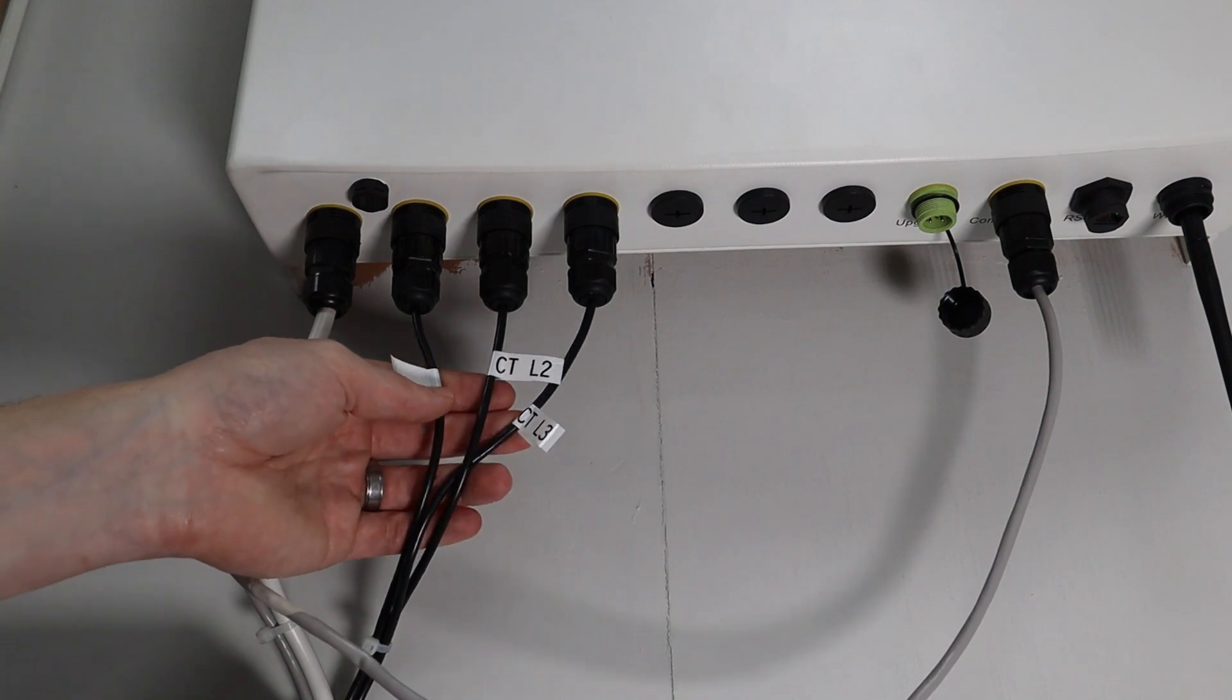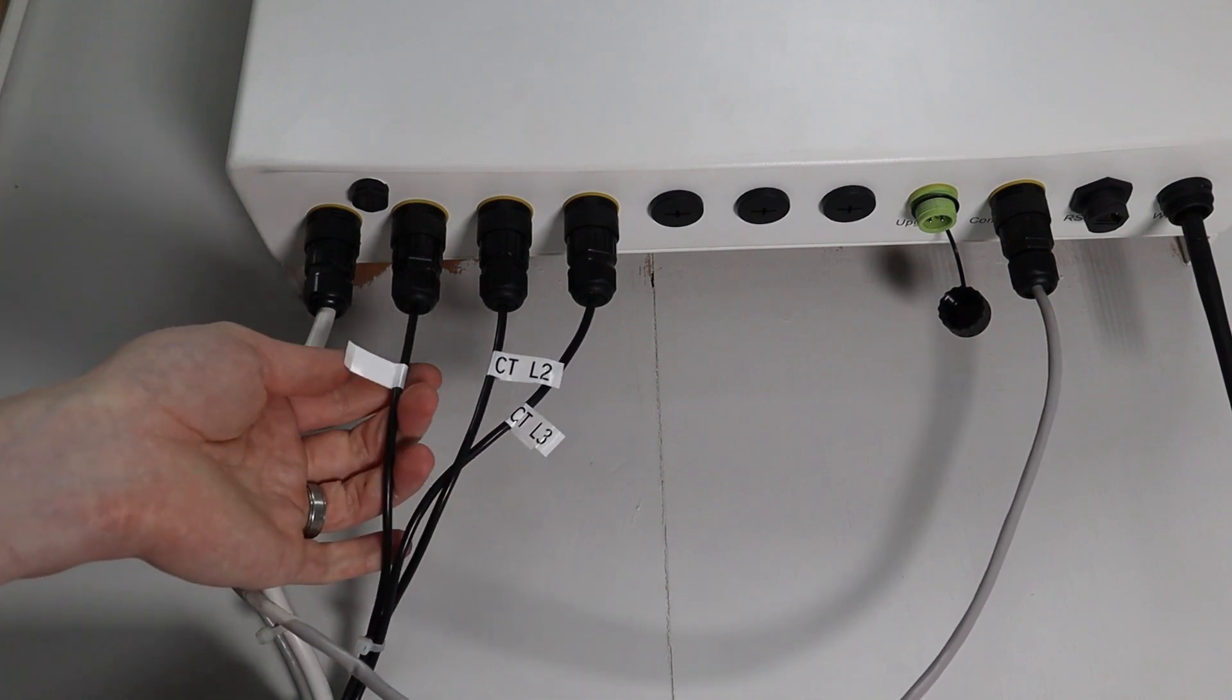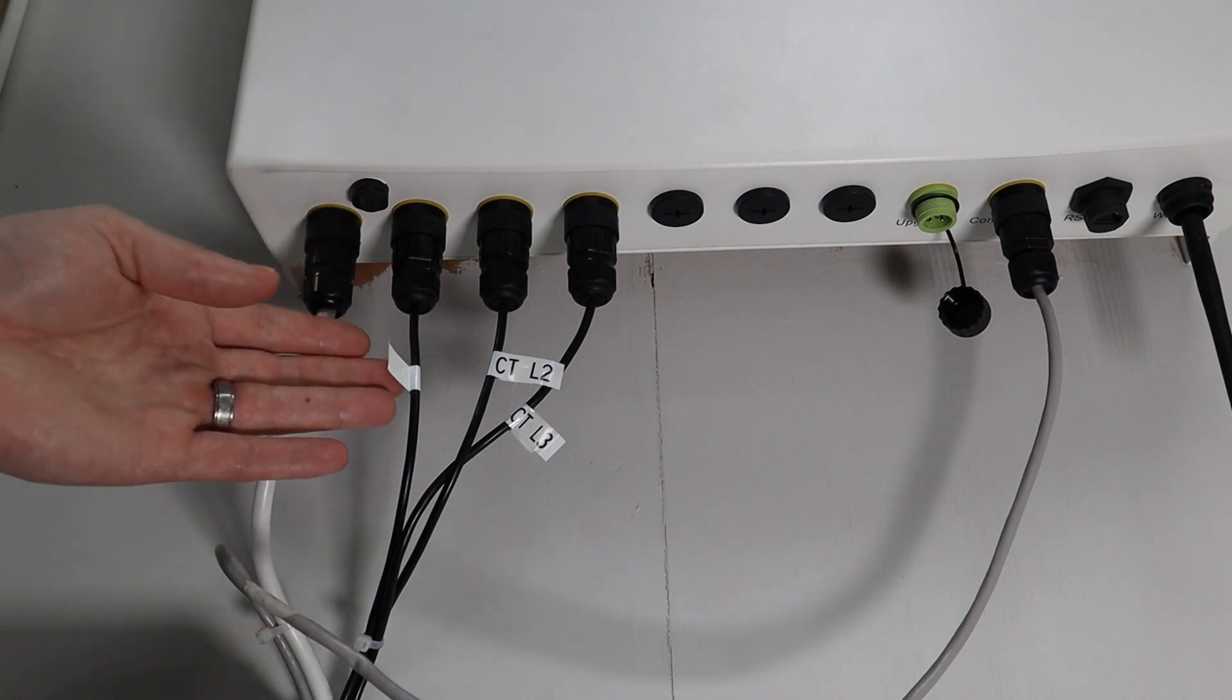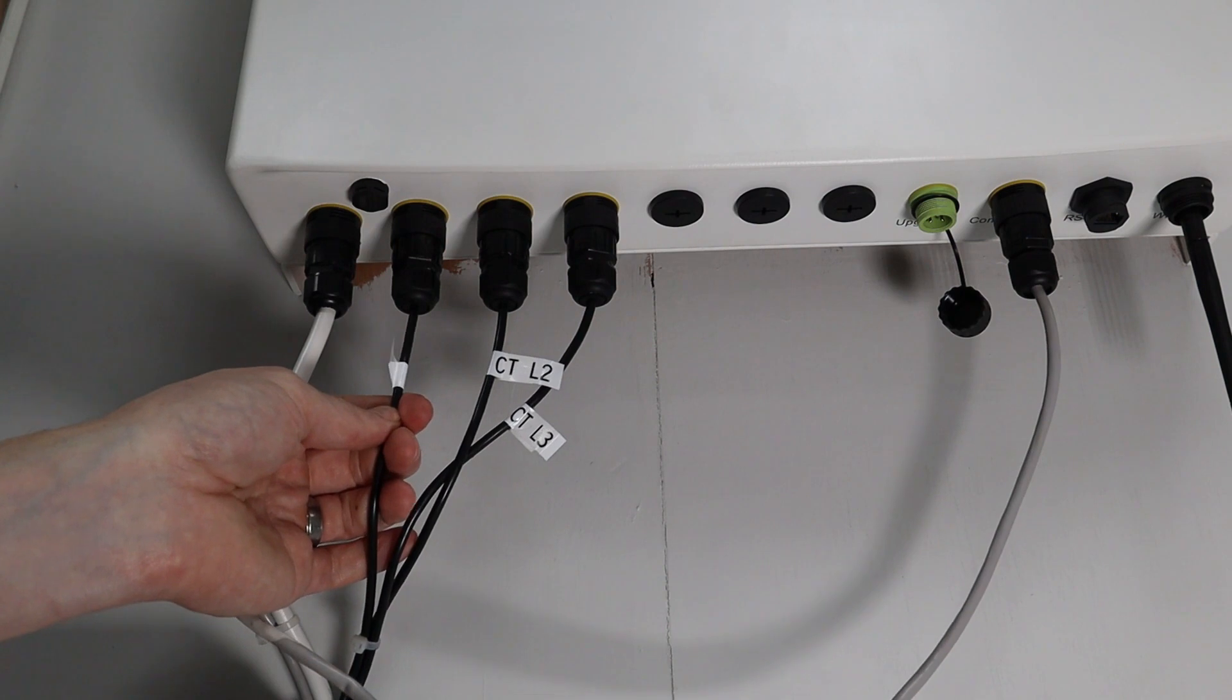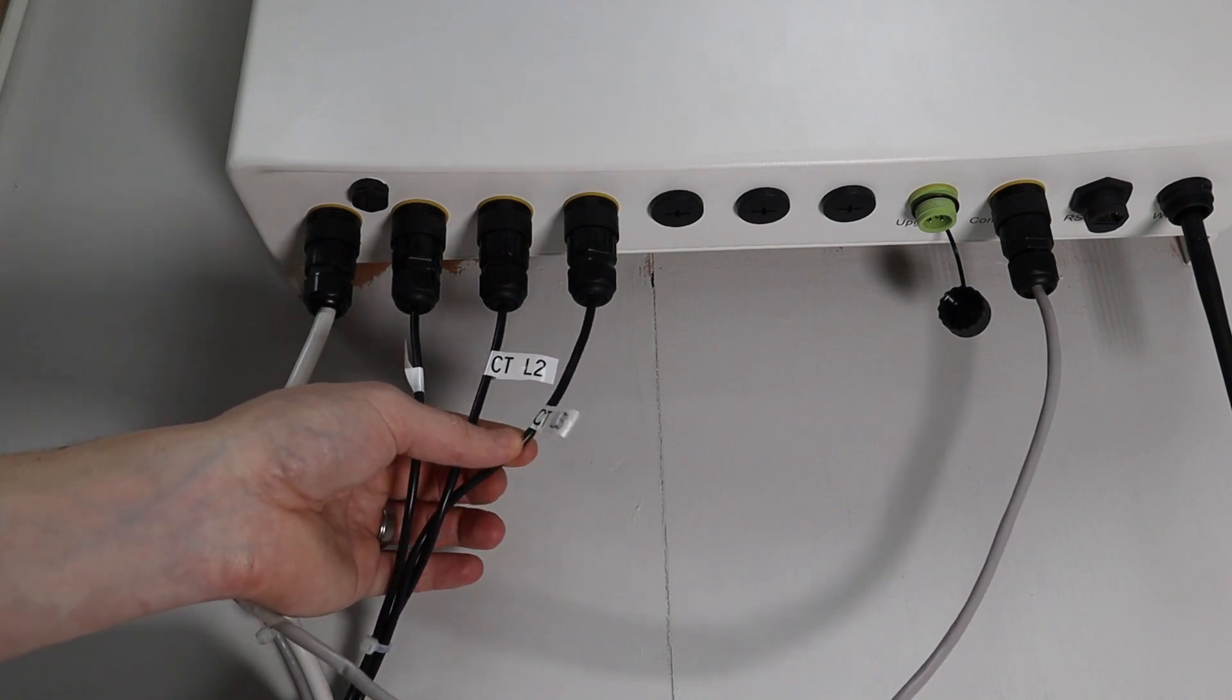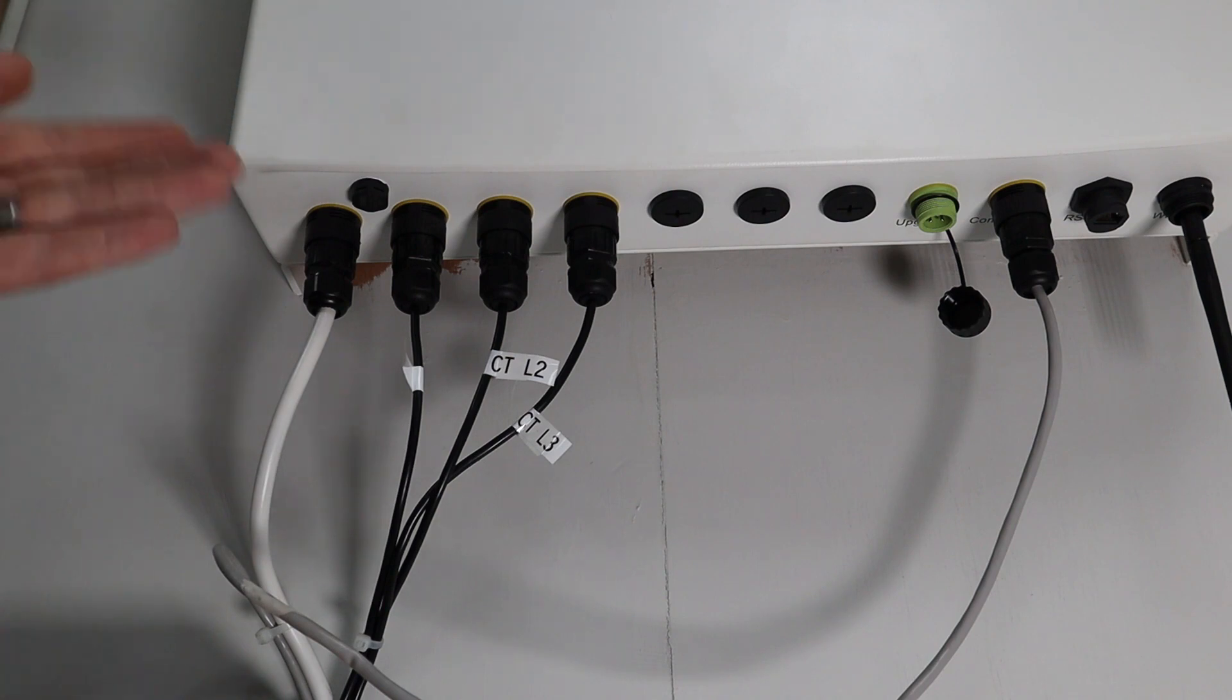And then moving on to current. So this EPM needs voltage and current to measure power, the real-time power of the grid. And these CTs are physically connected on the grid connection. It's very important that they're connected at the grid connections so they can monitor the consumption in the building as well as the PV inverter generation. And just as the voltages are important, it's very important that you match CT1 is on phase one cable and CT2 is on phase two and CT3 is on phase three. Again, if you mix those up, you'll be getting a bad power factor. It won't be measuring the real power correctly and the EPM will not be able to do its job correctly.